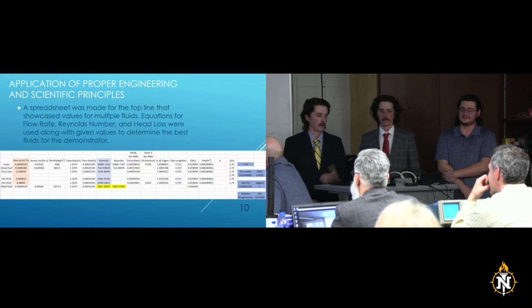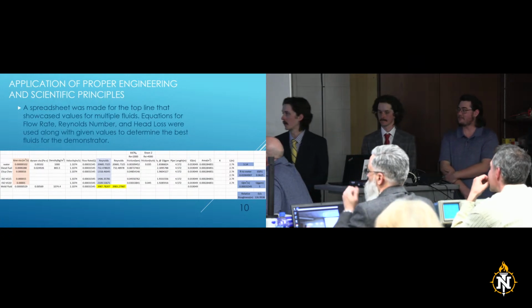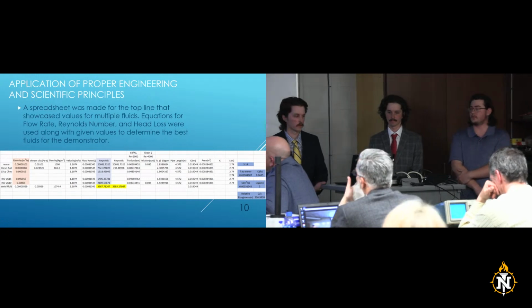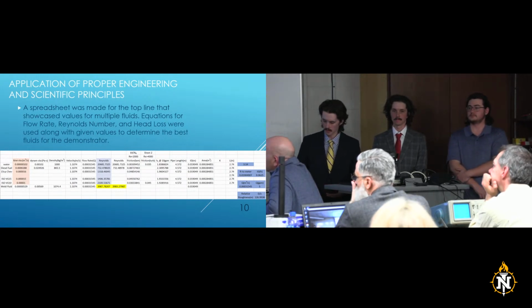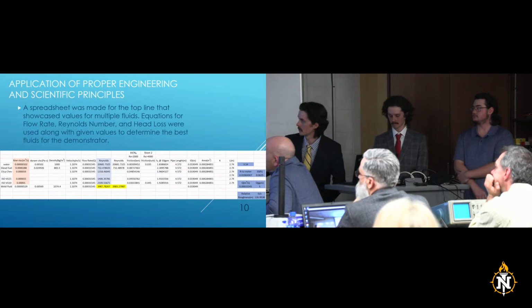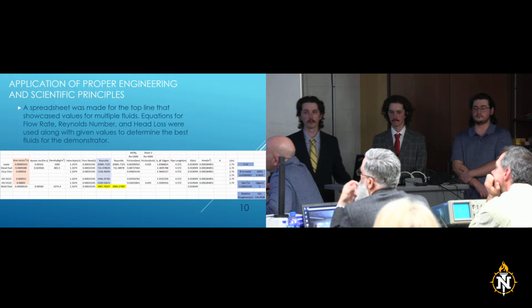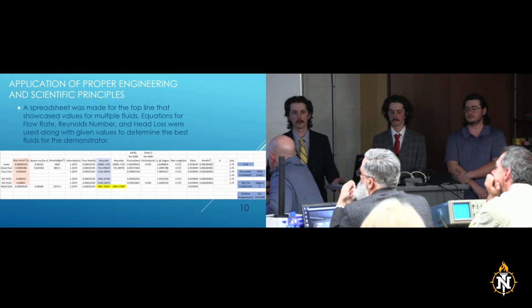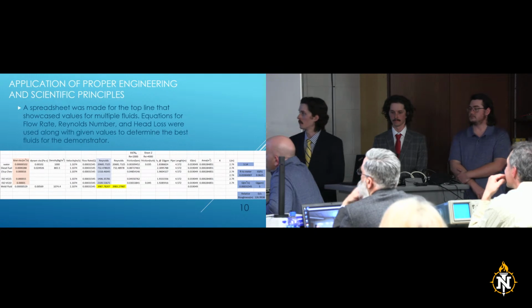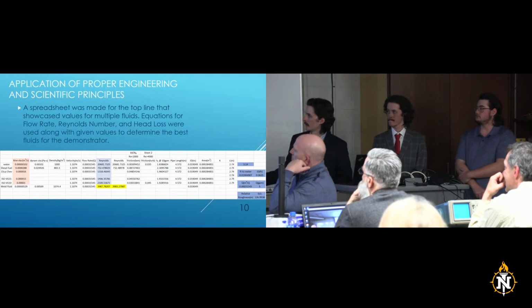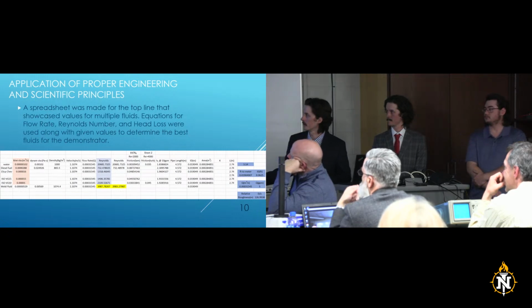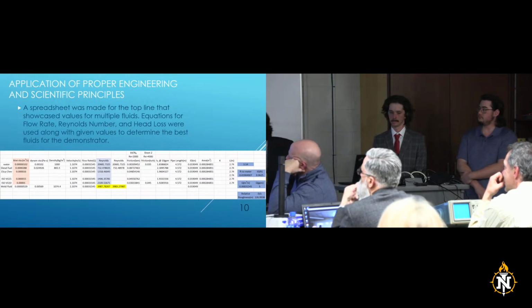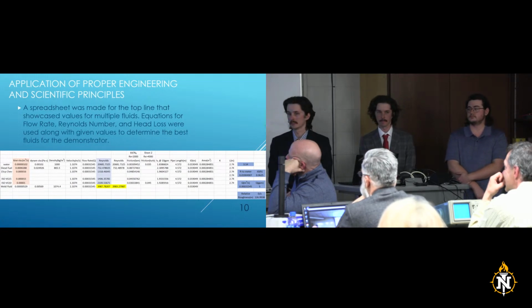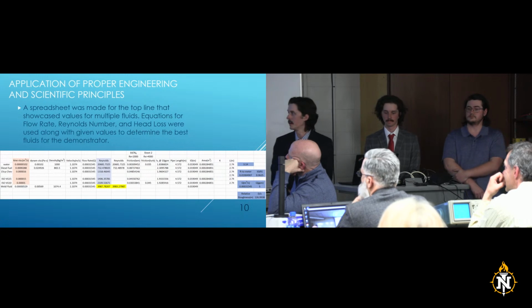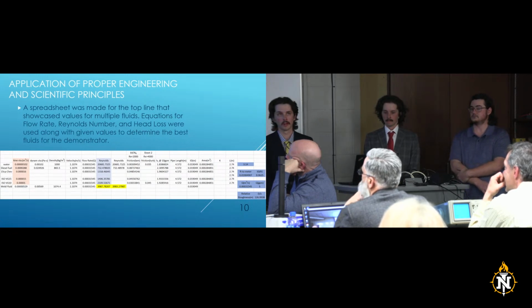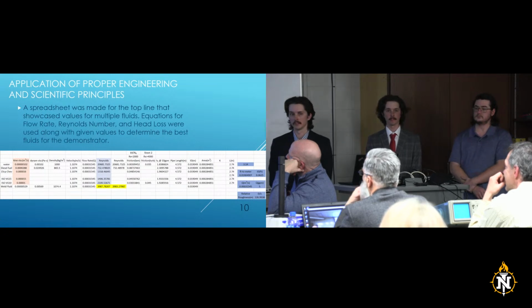So for our application of proper engineering, I made a spreadsheet for our top line that had various equations for flow rate, Reynolds number, and head loss. Here we have our Reynolds number. This determines if we have laminar flow, which is a smooth, clean flow, or turbulent flow, which is bubbly and disturbed. For water, we currently have on this spreadsheet 5 gallons per minute. We have a Reynolds number of, I believe, 20,000 at 5 GPM, which is a high Reynolds number for a fairly low flow rate. Our variable speed drive allows us to go down to a much lower flow rate and achieve laminar flow, which we'll show in a second.